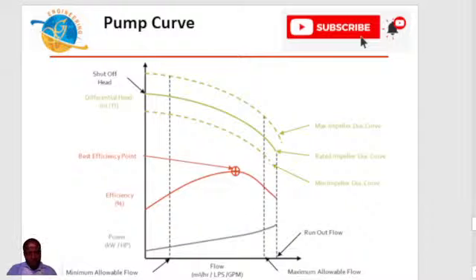Now, same way, the OEM will also specify in case you change the impeller diameter to the maximum impeller diameter, which will have been shown on the pump curve. The behavior of the pump will not be like the rated impeller.